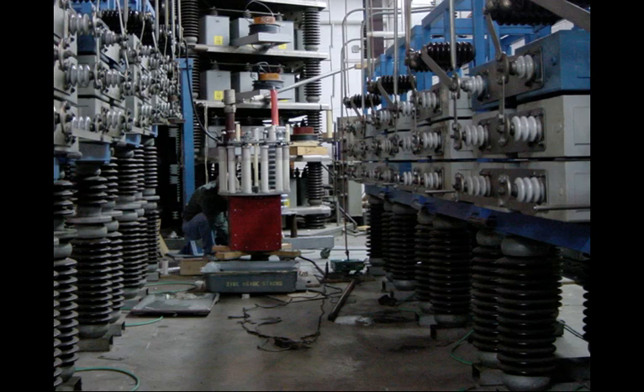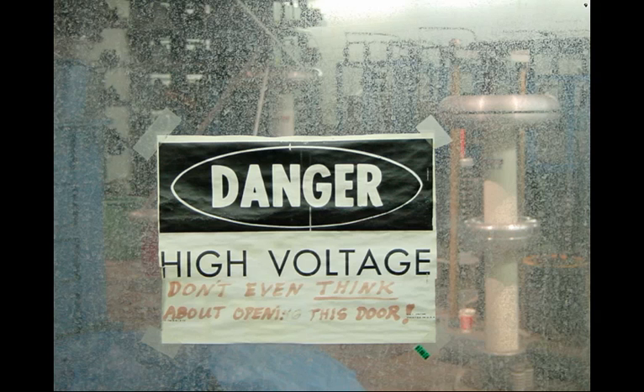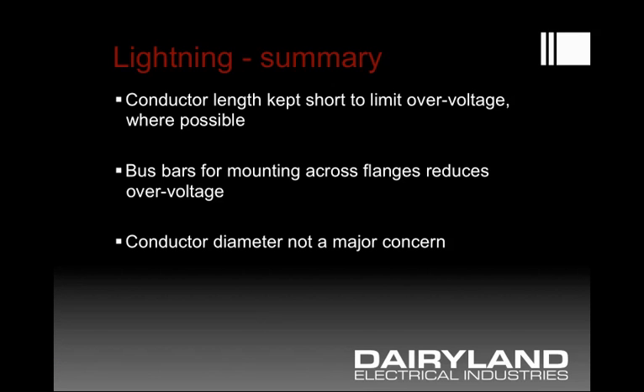This kind of apparatus can produce quite high levels of lightning current — so much so that you have warning signs on the doors. The key factor in lightning protection is to limit conductor length as short as possible to limit the resulting overvoltage.